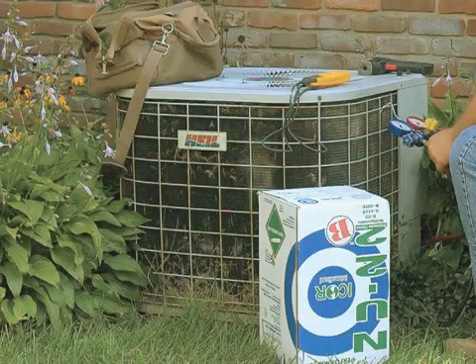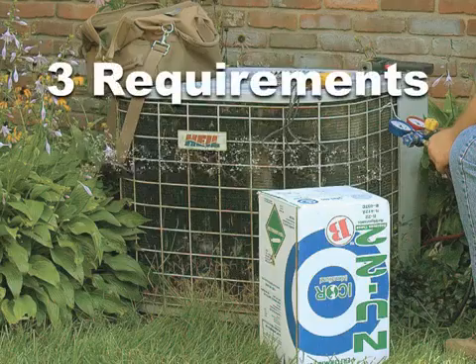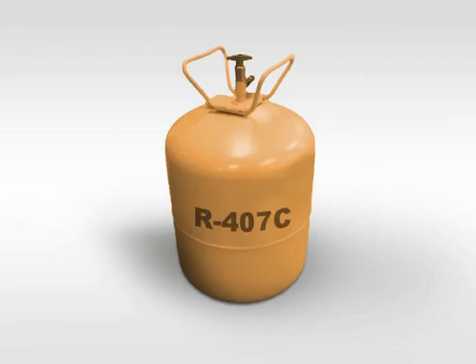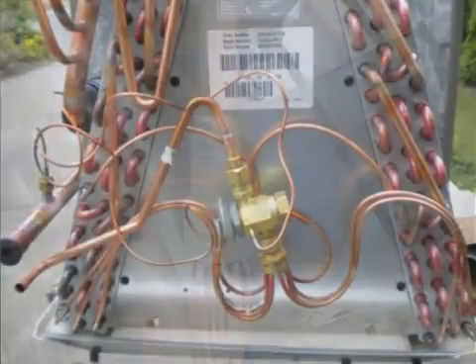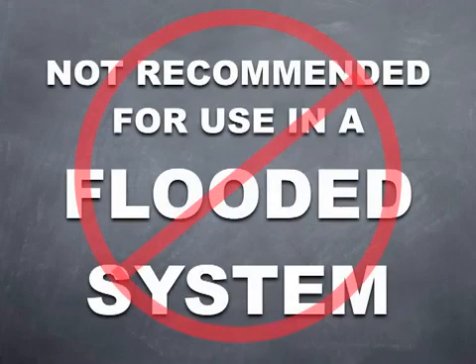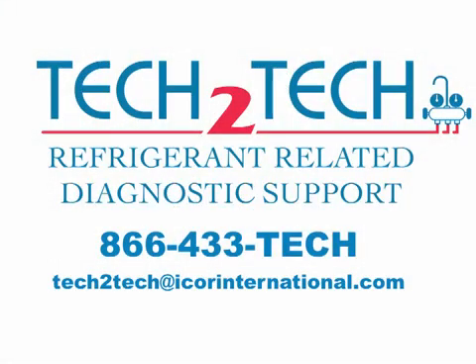Icor recommends following these three requirements when considering retrofitting to NU-22B. First, the system must be designed for use with R22 or R407C, free of leaks and in sound operating condition. Second, NU-22B is designed for use in systems utilizing direct expansion metering devices such as TXVs, fixed orifice, or cap tube. Third, it's not recommended to use this product in a flooded system. If you have a unique application you're considering for retrofit, please consult with an Icor tech support member before proceeding.